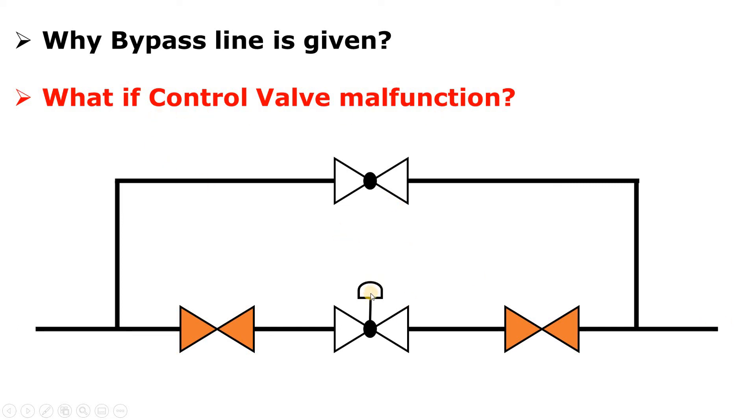And what if the control valve malfunctions? Let's suppose you have given the command of 50% opening and it is not opening 50%, it is opening only 25%. Or let's suppose if you are giving the command of 50% and it is opening 75%, so it is doing the malfunction. You will have to attend it.